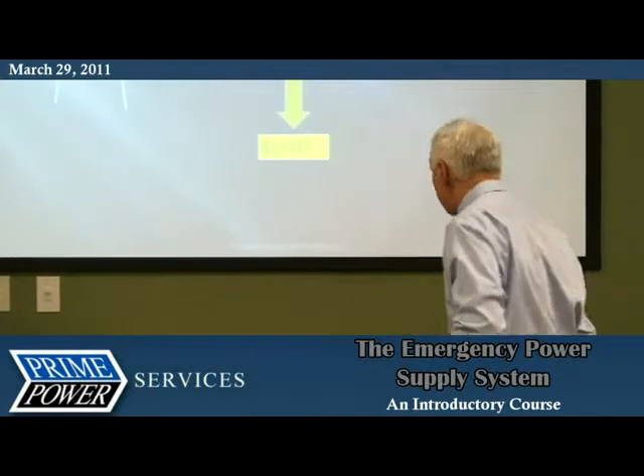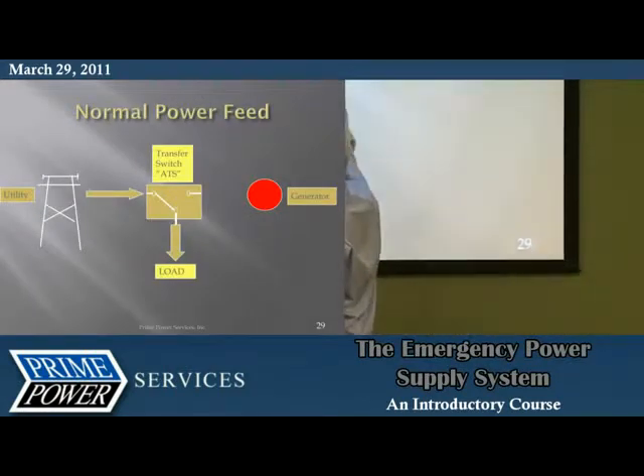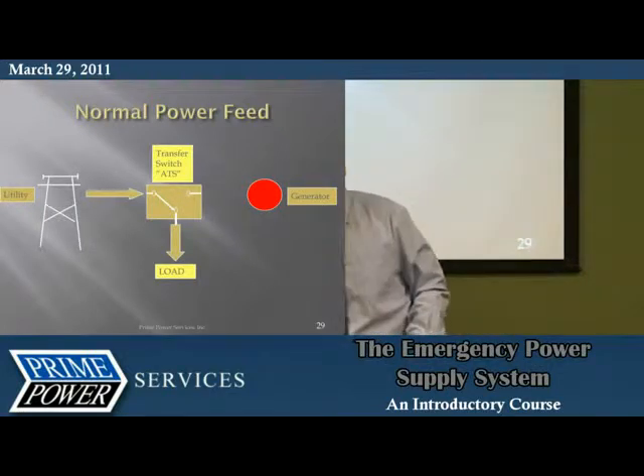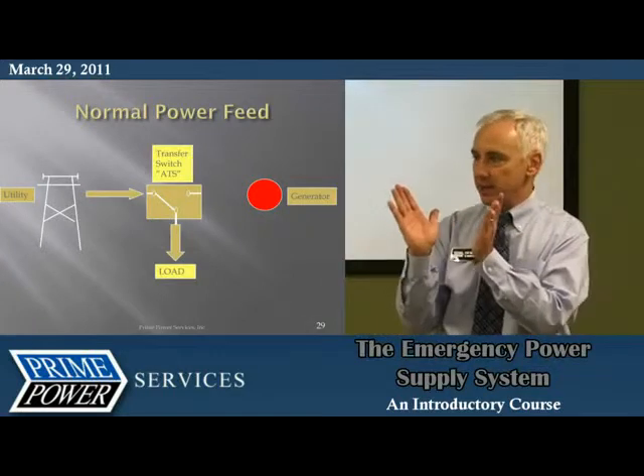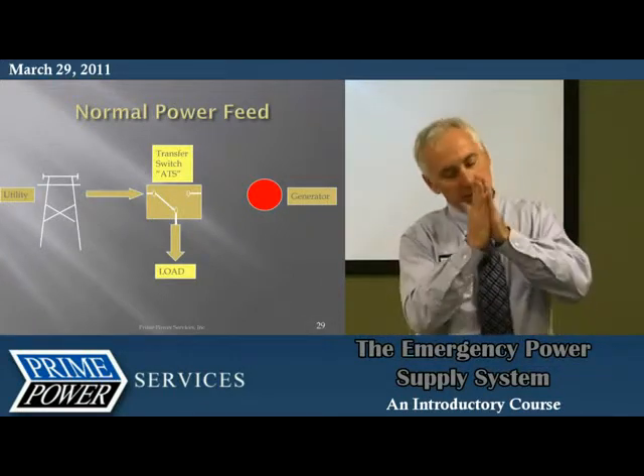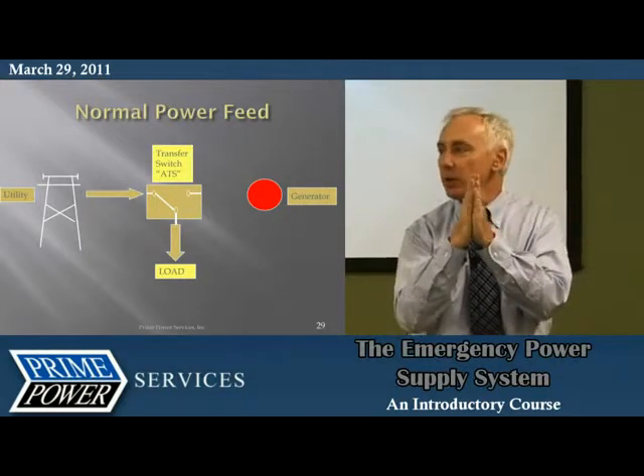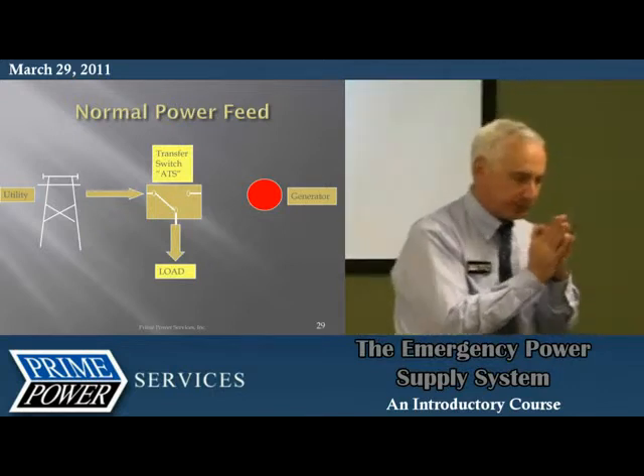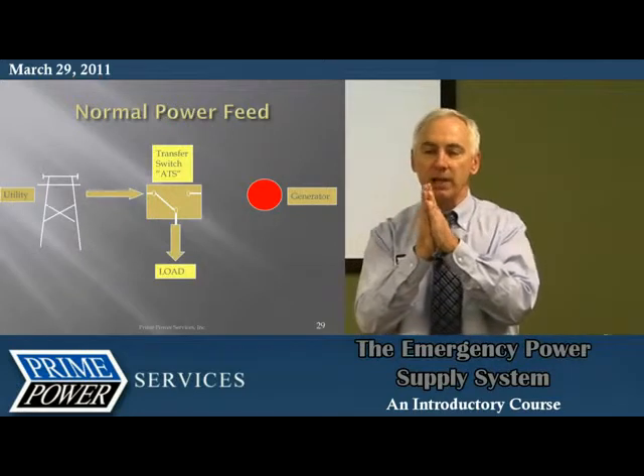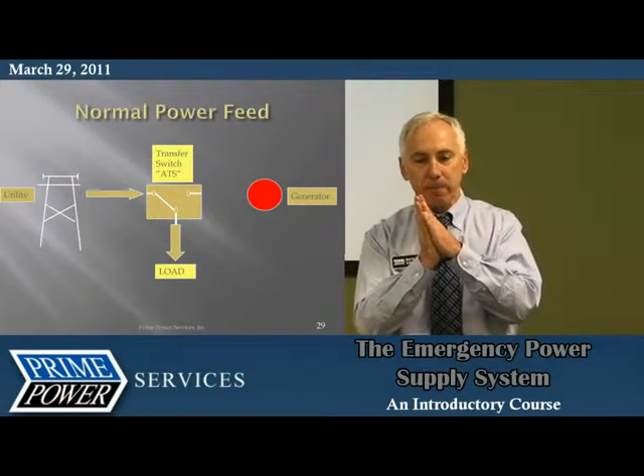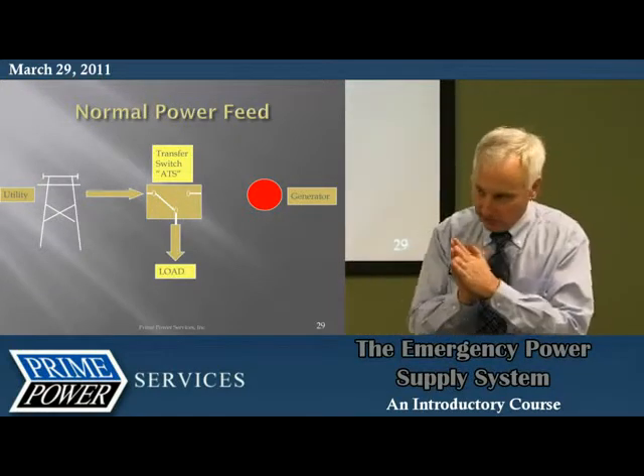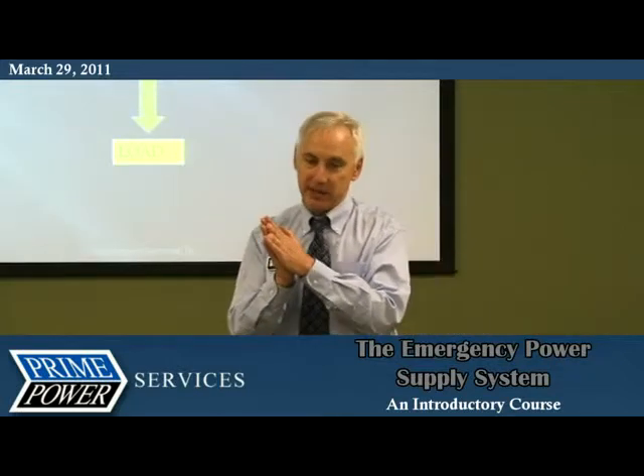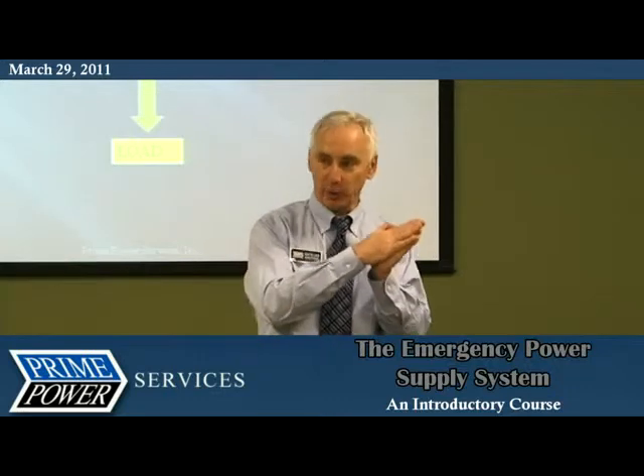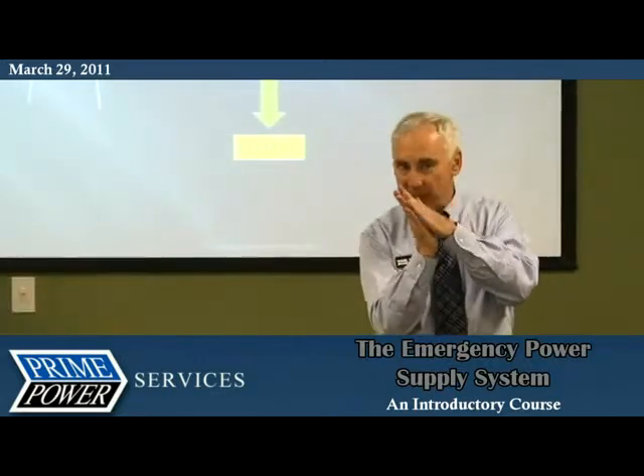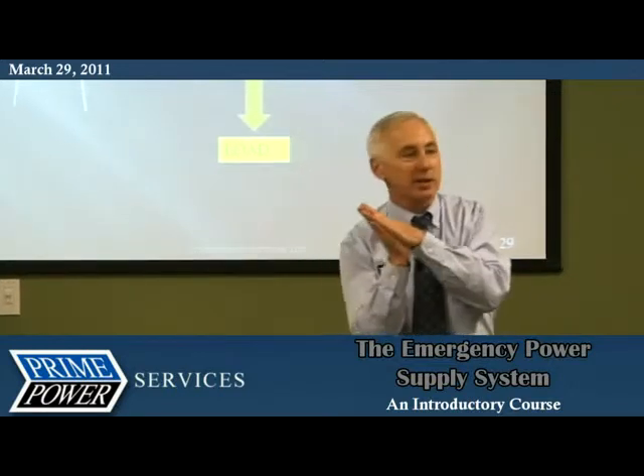These particular contacts are silver plated, and if this set sits open for a year or more, they'll oxidize. So the first time they come together, there's oxidation between the contacts, and they start to overheat. Overheating is unique because hotter contacts have more resistance, so they heat up more, which gives them even more resistance, so they heat even more. It builds on itself once it gets going.